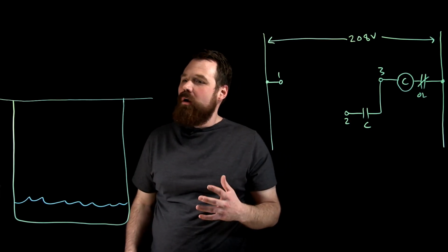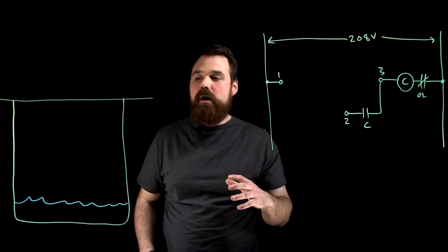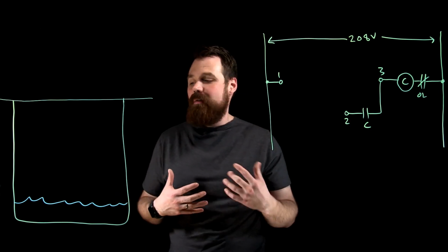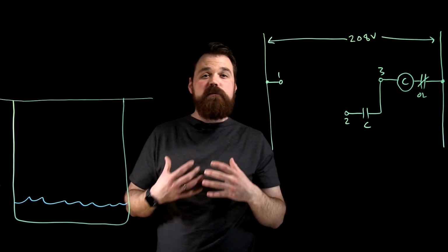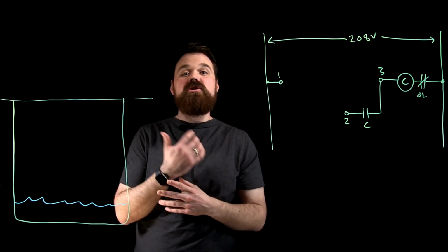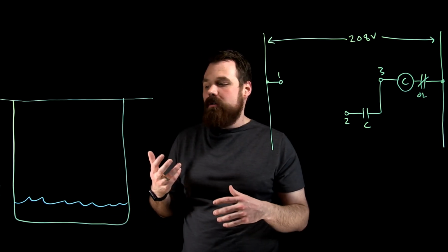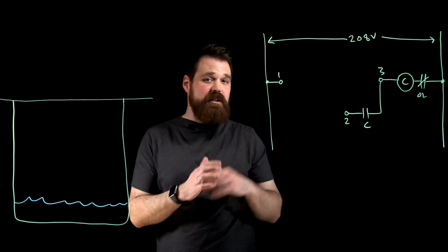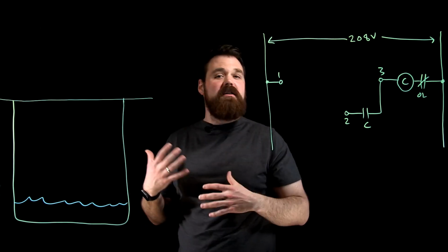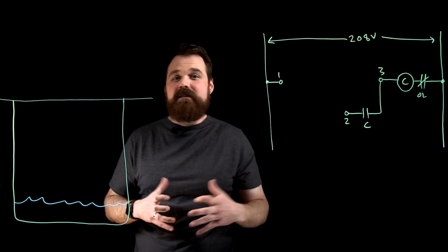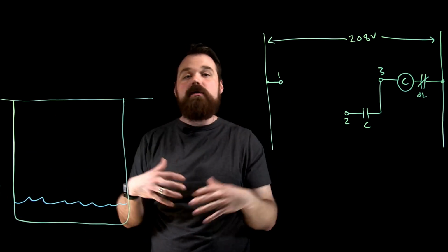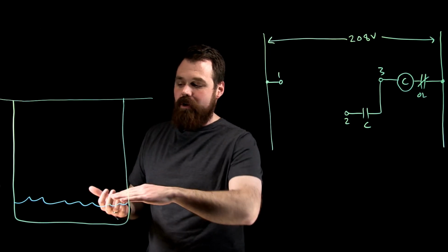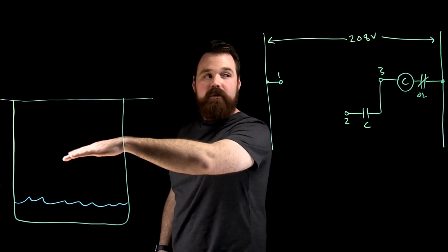Hi. So I want to talk in this video about designing a control circuit that would be used to drain some type of tank. Now this is a really common application for sump pits. If I'm dealing with a sump pit, especially in a commercial environment, think about underground parkades, anything like that near the water table, they'll have a sump pit in the basement where all the drains will drain into. What'll happen is the water inside that sump pit will fill up.